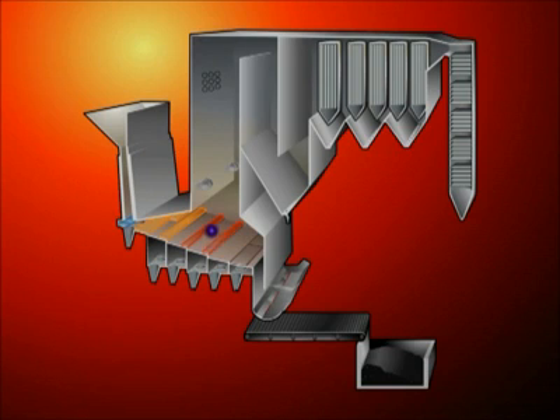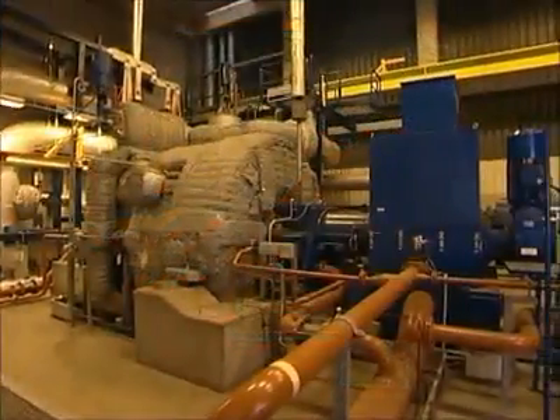The oxygen from primary air brought into the grate from below makes the fuel burn. The hot gases move upwards in the body of the furnace, where more oxygen is added in the form of secondary air for complete combustion. To reduce the nitrous gas emissions, ammonia solution is added in what is called an SNCR system. The body of the furnace is made up of tubes in which the boiler water is evaporated by the heat from the combustion. The hot flue gases are further cooled down in the idling duct before they continue to the superheater pack, where the steam is heated up to 36 bars and 380 degrees Celsius.